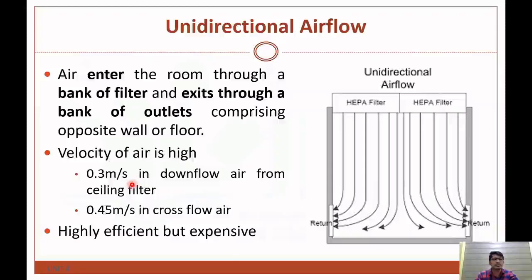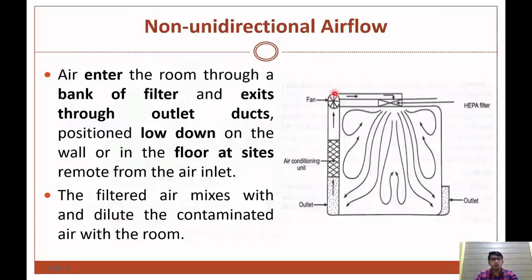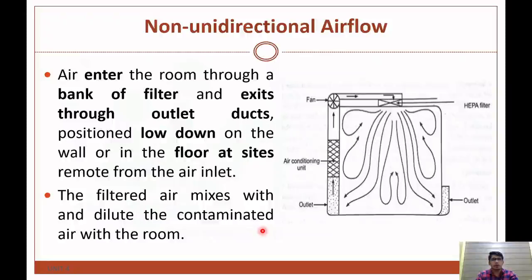The velocity of air in unidirectional flow is 0.3 meters per second in the downflow from the ceiling filter and 0.45 meters per second in the crossflow. This system is highly efficient but expensive. In non-unidirectional flow, air enters through a bank of filters and exits through outlet ducts positioned on the wall or floor at the side removed from the air inlet. The filtered air mixes with and dilutes the contaminating air within the room, which is the main problem with non-unidirectional air flow.